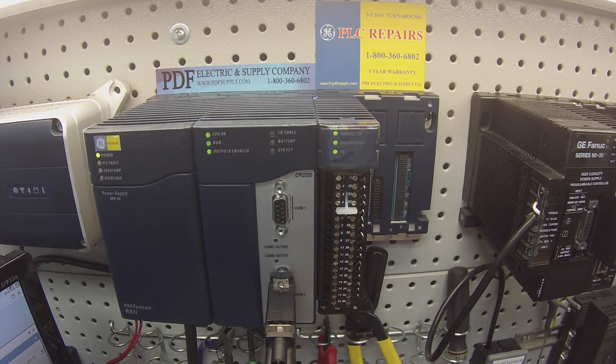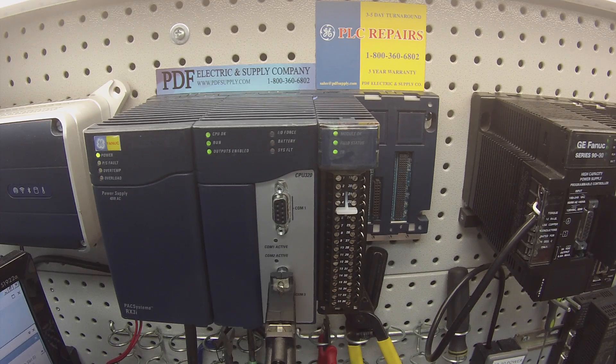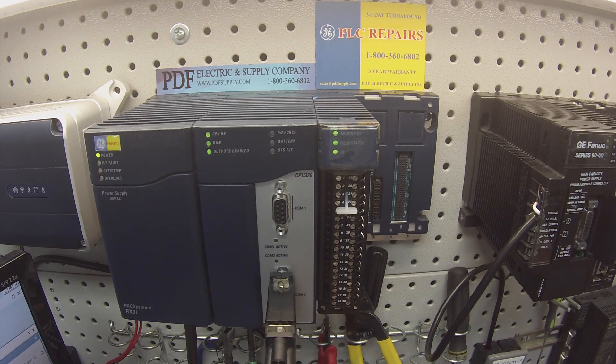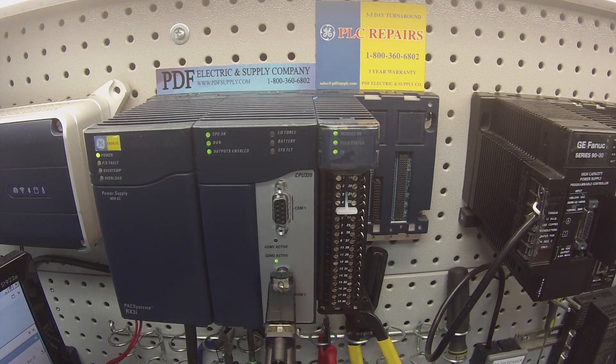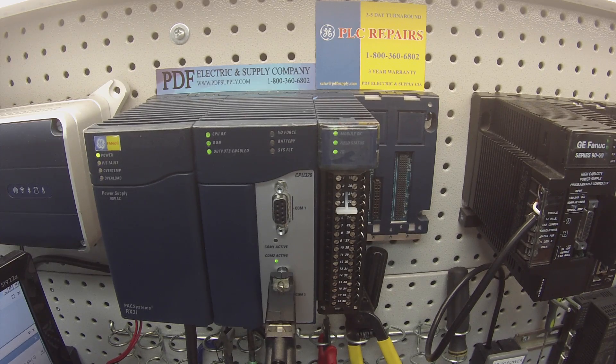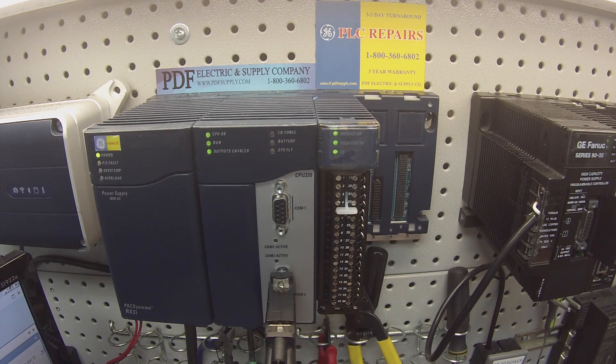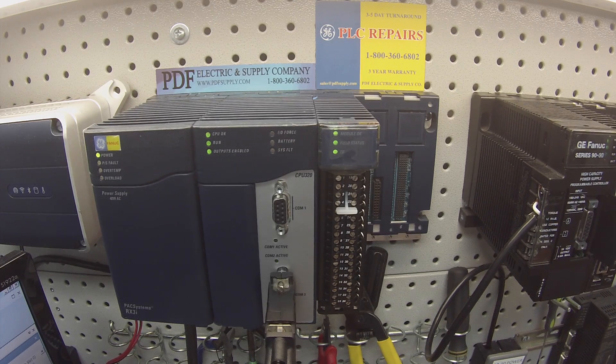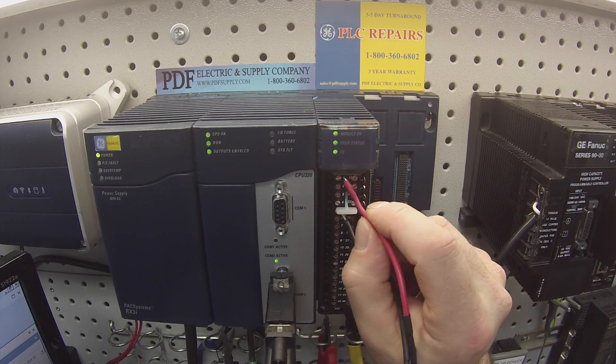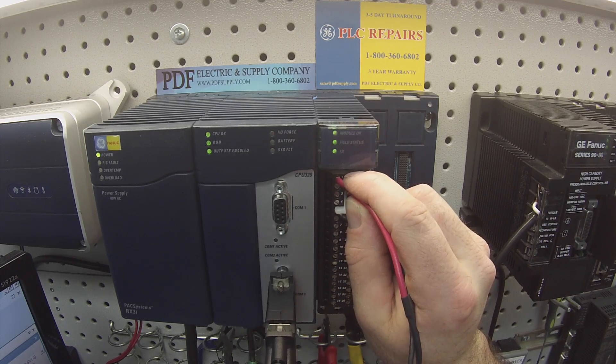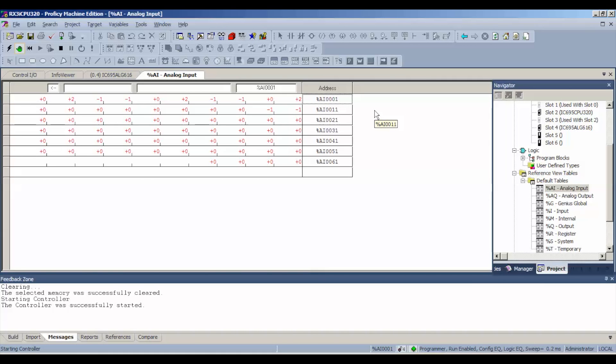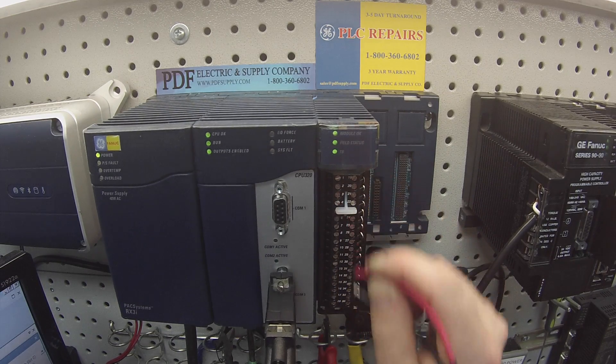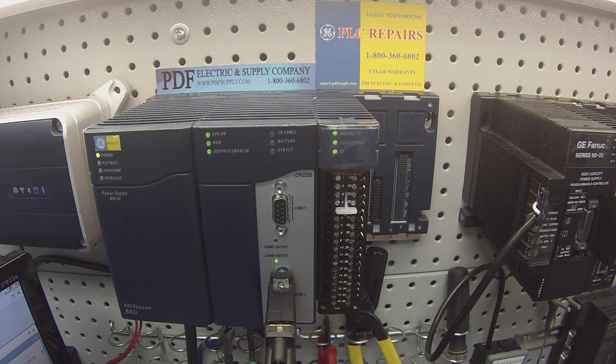If you go by the diagram on the inside of the door, you'll notice that the common terminal is number five, and the first four channels are screws on the left hand side - one, two, three, and four - and it's descending after that. Terminal six is channel five, terminal seven is number six, and so on. We're probing in a vertical pattern, meaning that the channels are all up and down rather than left and right. Now I'm going to plant my negative lead on number five and my positive lead on number one, and immediately I have a value of, depending on your scaling, 2145. Probe number two, approximately the same value, it's stable. Number three, number four, and I can keep going all the way down. Just make sure that your negative lead is planted on one of the commons.